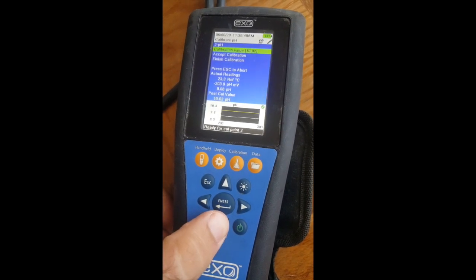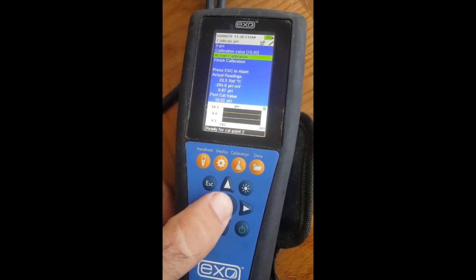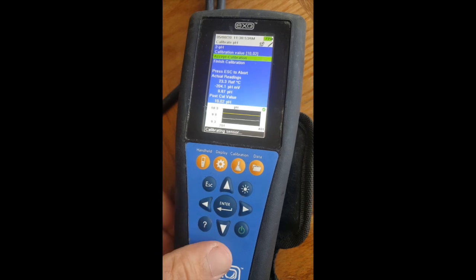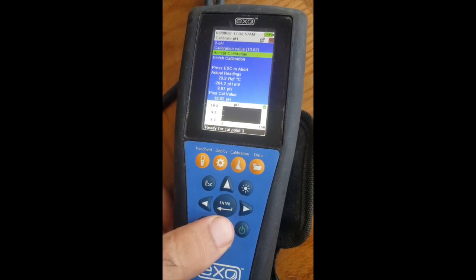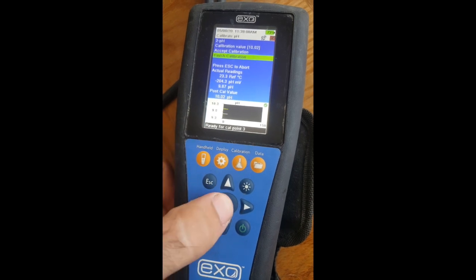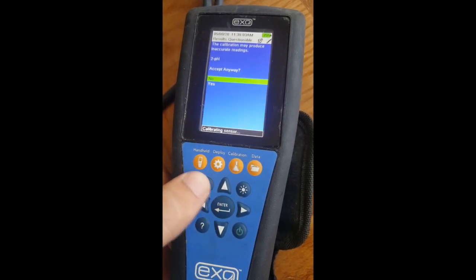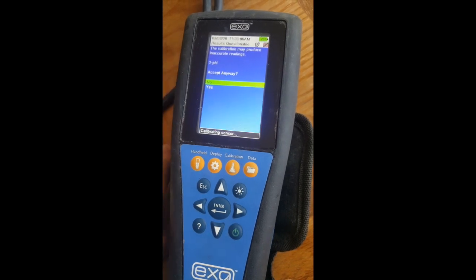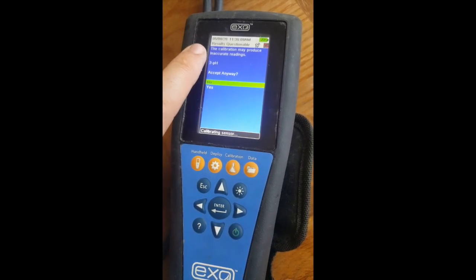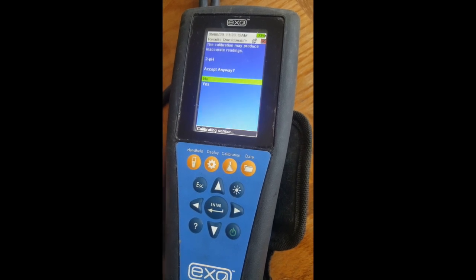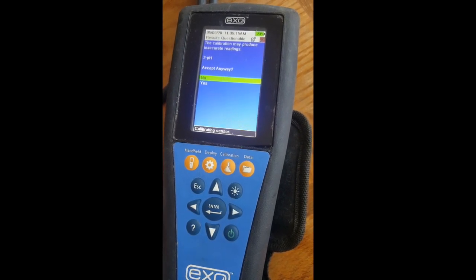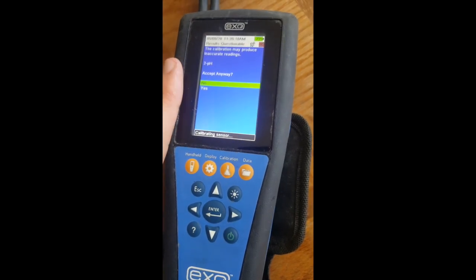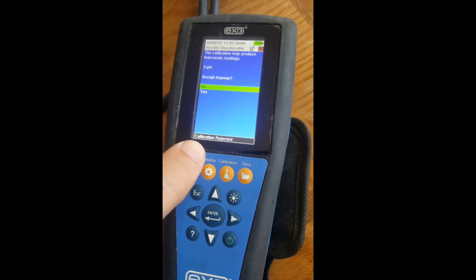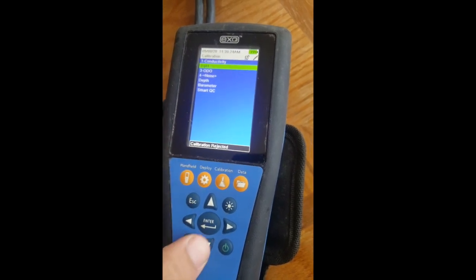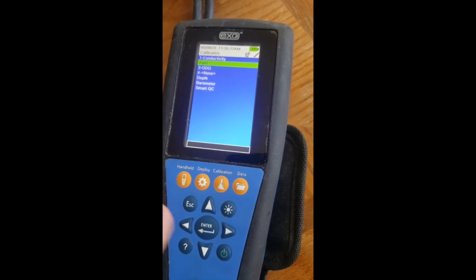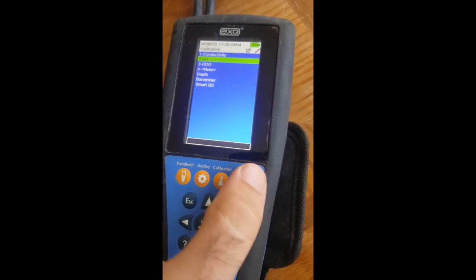After it does stabilize, we're going to accept the calibration value, and then we're going to finish. Now this has a QA reading on it saying that my calibration may produce inaccurate readings because our pH readings and the calibration readings were so far off. So again, if this does come up, push no, and it'll reject your calibration. Now, if it does accept it, it'll give you a summary of what happened. So I'll pull that up.